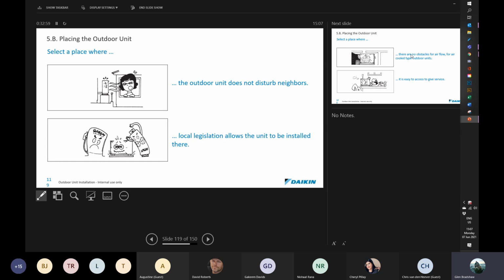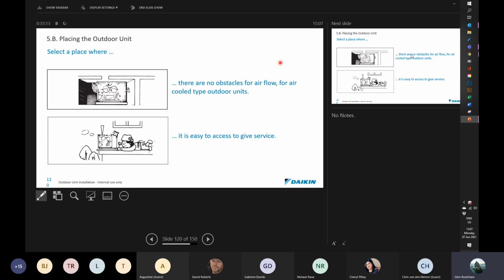If you have concerns on site, when you see the placement of a condensing unit, and I have seen condensing units placed very, very close to gas installations, you should make the relevant people aware of it, especially at the installation. Okay, just in case changes need to be made. Okay, make sure that there's no obstacles around the condenser for airflow. Condensers, just like indoor units, do not like air recirculating. All right, also make sure that there's easy access for service. We don't want to see service engineers dangling on the end of buildings just to be able to work on a unit.